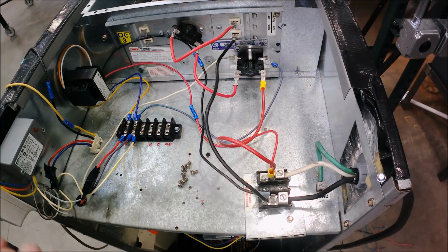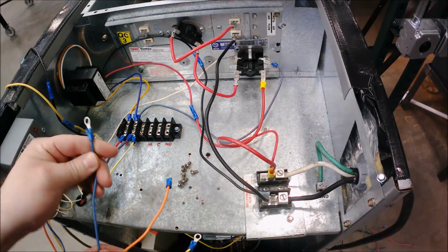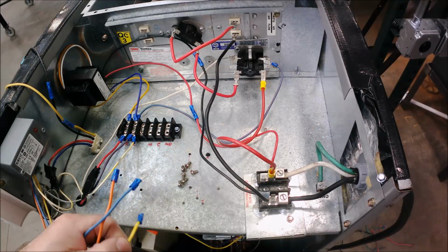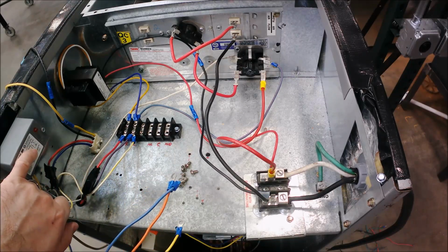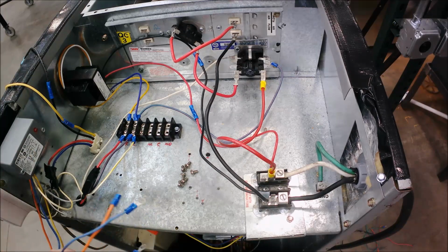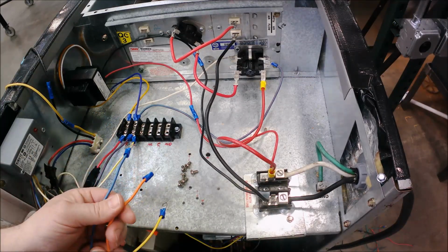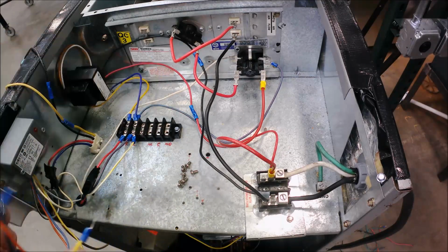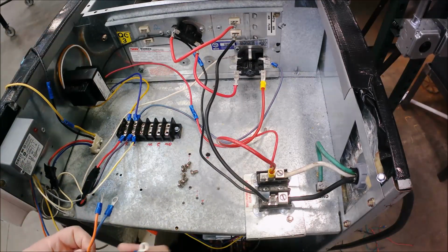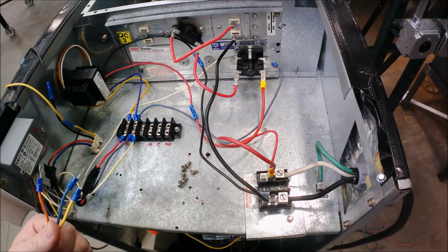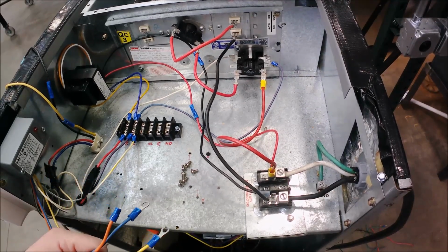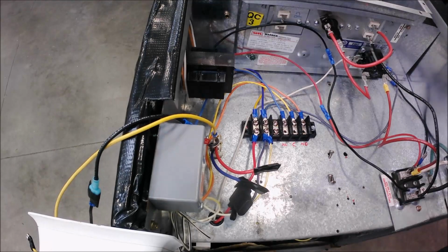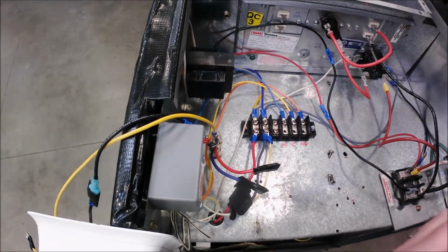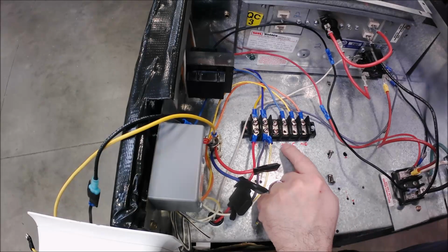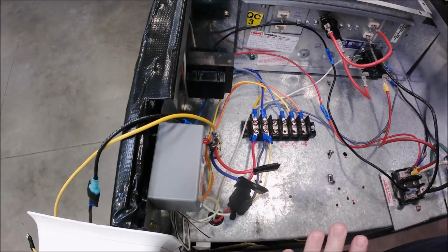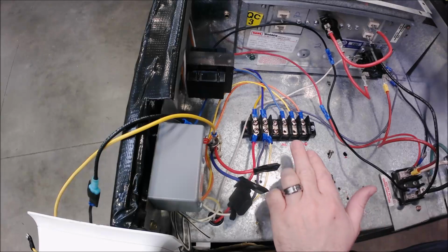So as we're looking at this, what I've got off the rib relay is I've got these solid color wires. I've got a blue, an orange, and a yellow. And if you look, yellow is common, the blue is normally closed, and the orange is normally open. And I'm going to attach these to that terminal block, and instead of using wire nuts, like I said, it's going to be a little bit easier when we do voltage checks. Alright, so let's look at the rib relay and how we're going to wire up the fan through this. Alright, so we got normally closed, common, normally open. I've already terminated the rib relay side of things.